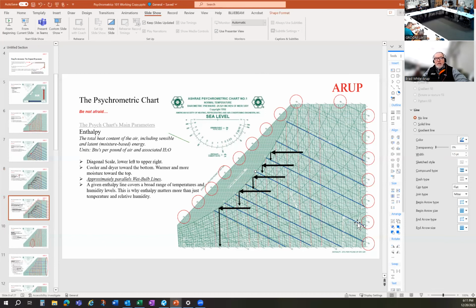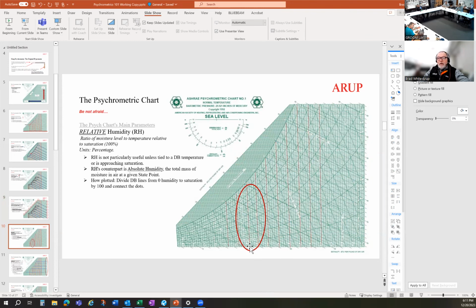Now, relative humidity, again the most misused term in HVAC engineering, is how close you are to saturation at a given temperature. If I'm at a given temperature with X amount of moisture and I'm at 50%, that means I'm halfway to saturation. If I double my moisture, I'll be saturated. If I drop it to zero, I'll be at zero.